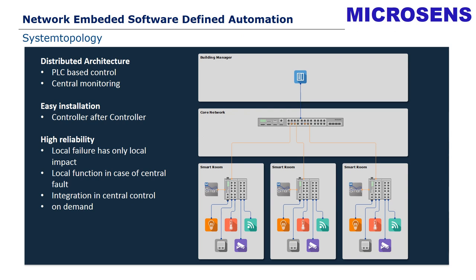Typically for this structure is a distributed architecture which is PLC-based, where automation runs at the PLC level, and central monitoring is provided at the management layer. We have easy installation — because it can be done controller by controller, room by room, during a running system. This also provides high reliability, since if a failure happens, it only impacts the local unit that created the error. The devices can be integrated into a central control on demand, enabling step-by-step building automation.